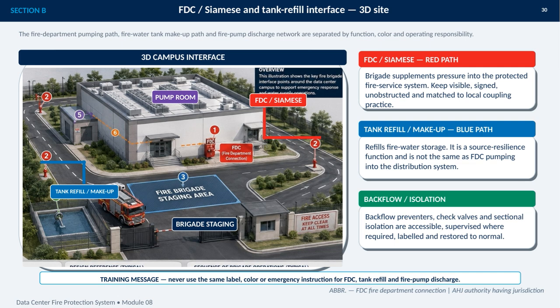The tank refill or makeup path serves a different purpose. It restores fire water storage and supports source resilience, but it is not a substitute for FDC pumping into the distribution network. The pump room and brigade staging areas should reinforce that distinction in both layout and training.